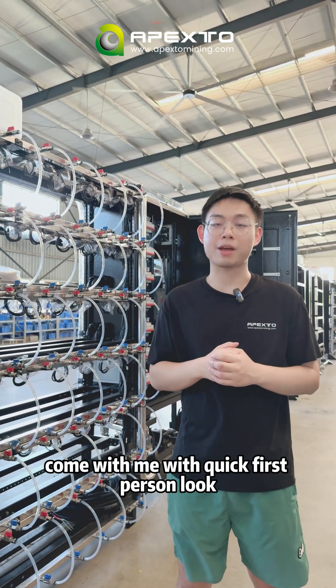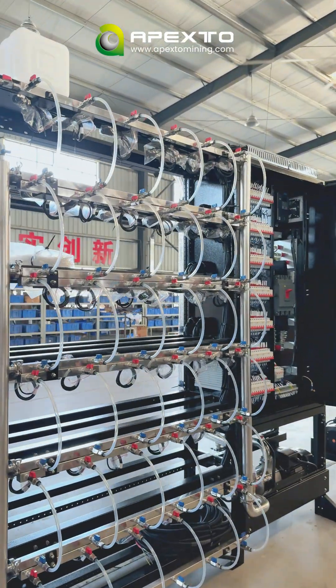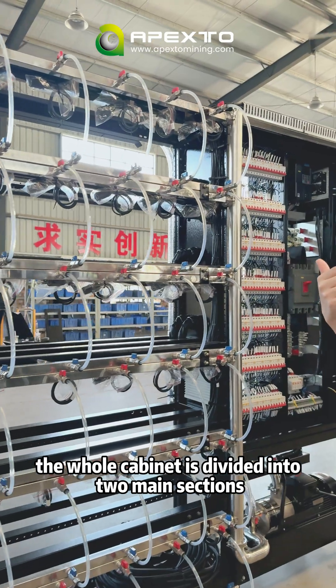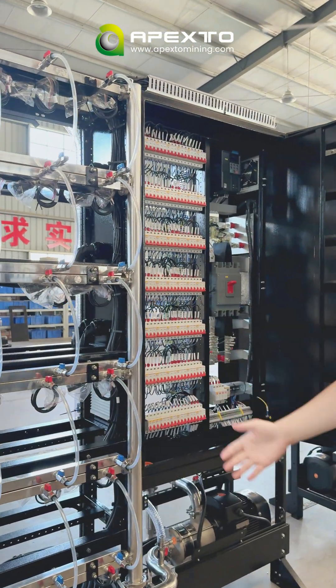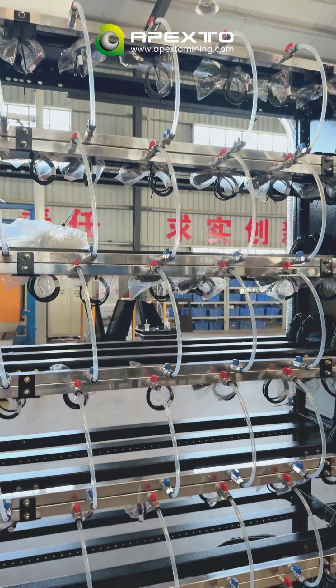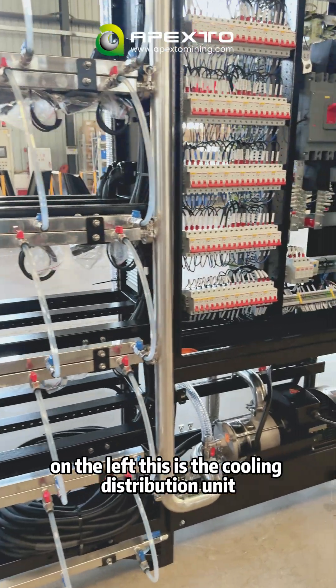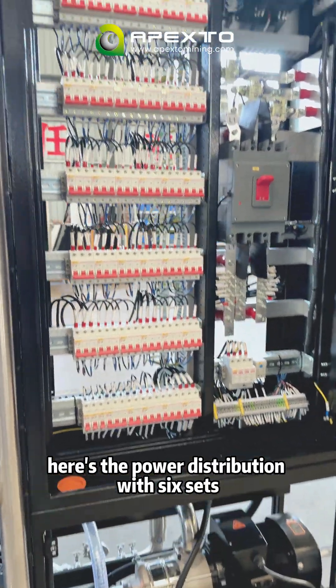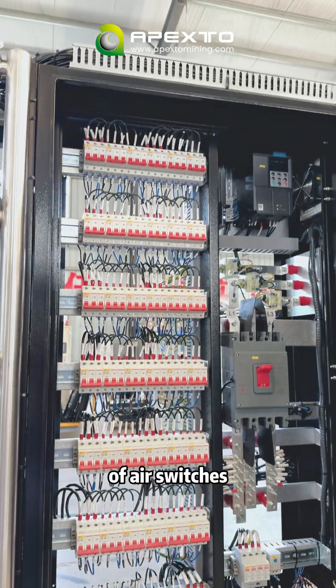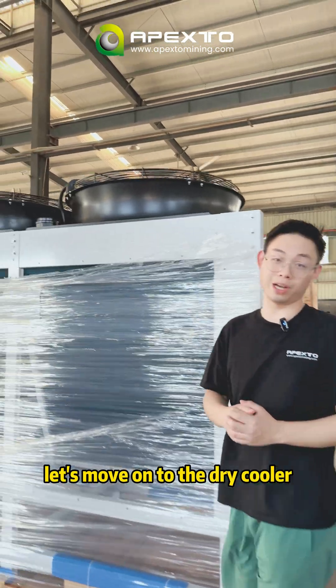Coming with a quick first-person tour. Here is the H200s setup. The facility is divided into two sections. On the right we have the rack where the hydro antminers are placed — 13 units in total. On the left is the cooling distribution unit, the power distribution with six sets of air switches, and down below you'll find the water pump.